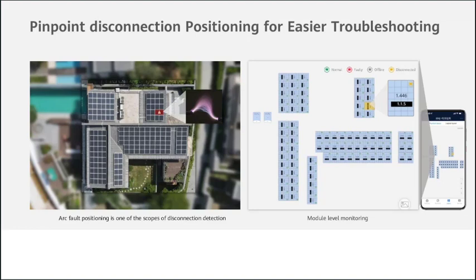All of our inverters come with an integrated arc fault circuit interrupter system, called AFCI, which automatically detects an arc on the roof. Even without an optimizer, we can detect these arcs on the roof using only our inverter.